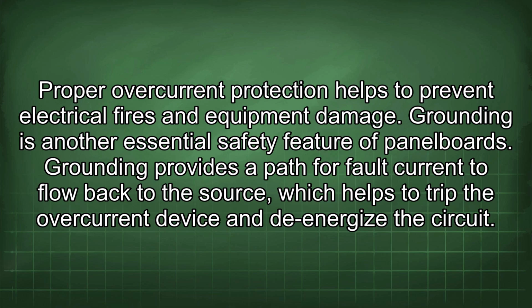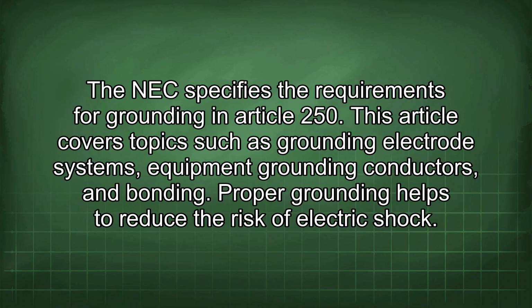Grounding is another essential safety feature of panel boards. Grounding provides a path for fault current to flow back to the source, which helps to trip the overcurrent device and de-energize the circuit. The NEC specifies the requirements for grounding in Article 250. This article covers topics such as grounding electrode systems, equipment grounding conductors, and bonding. Proper grounding helps to reduce the risk of electric shock.